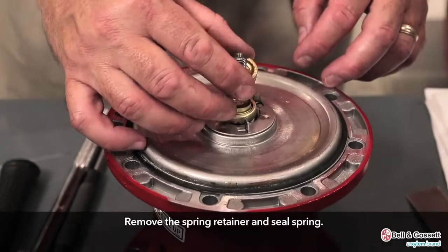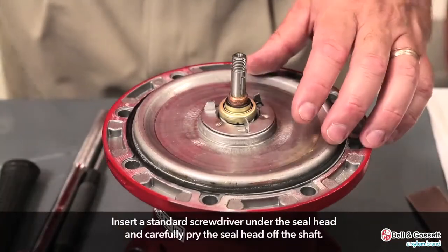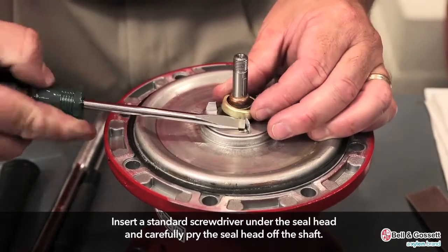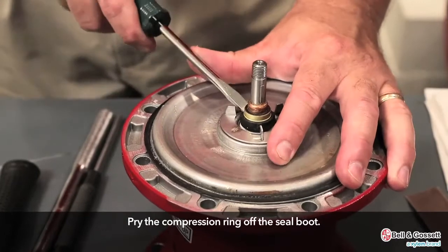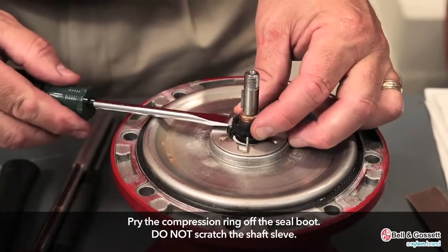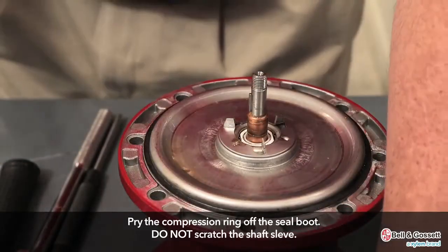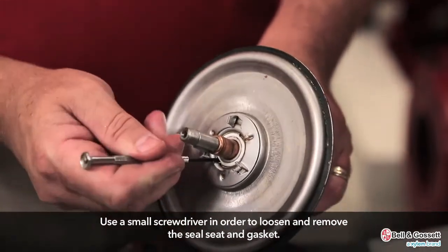First, remove the spring retainer and seal spring. Insert a standard screwdriver under the seal head and carefully pry the seal head off the shaft. Pry the compression ring off the seal boot. Be careful not to scratch the shaft sleeve. Use a small screwdriver in order to loosen and remove the seal seat and gasket.